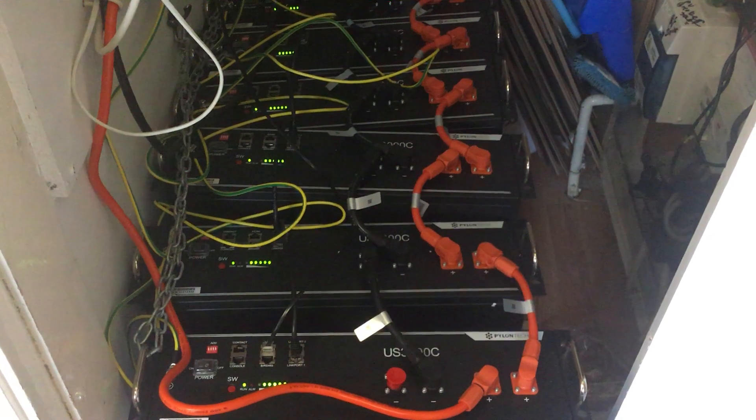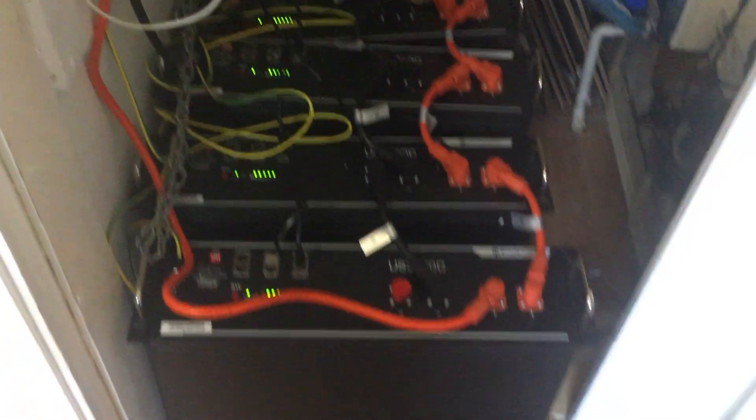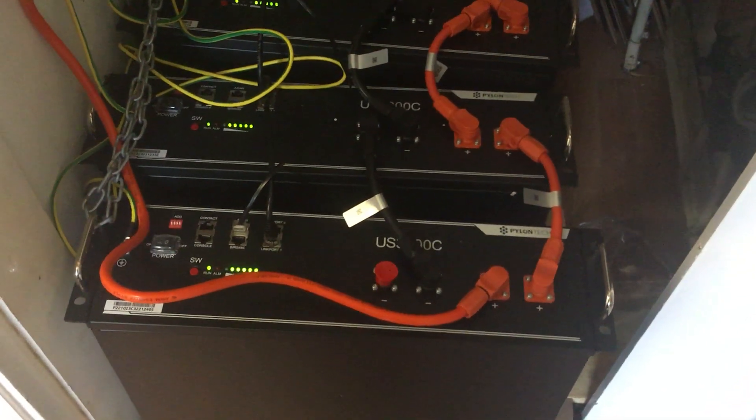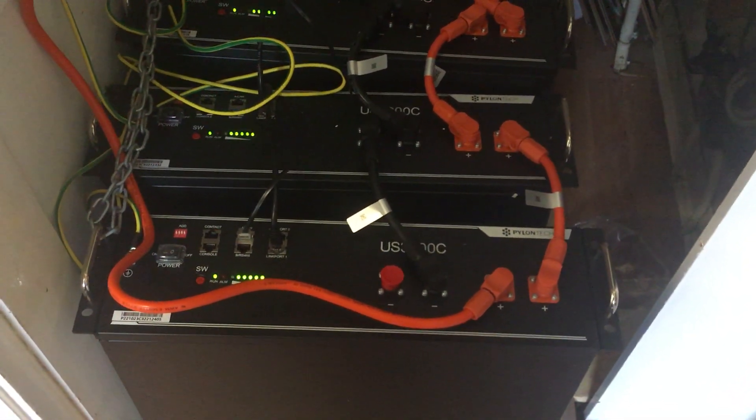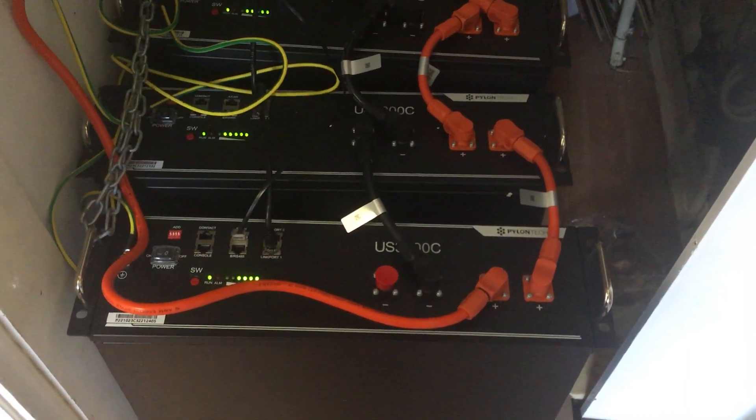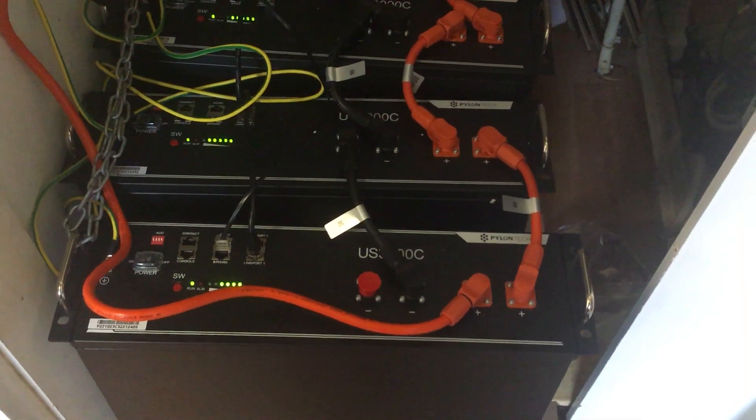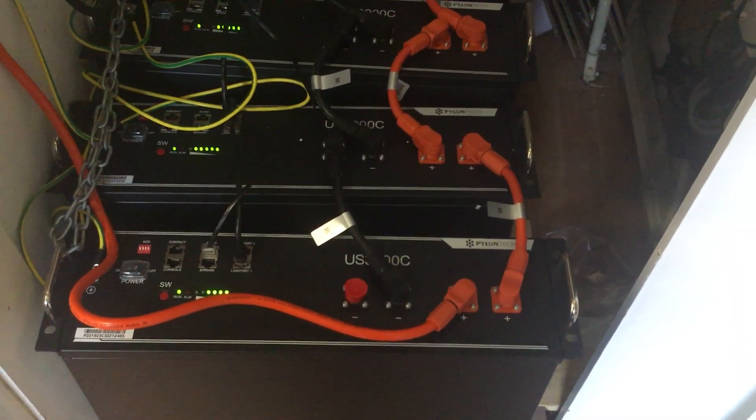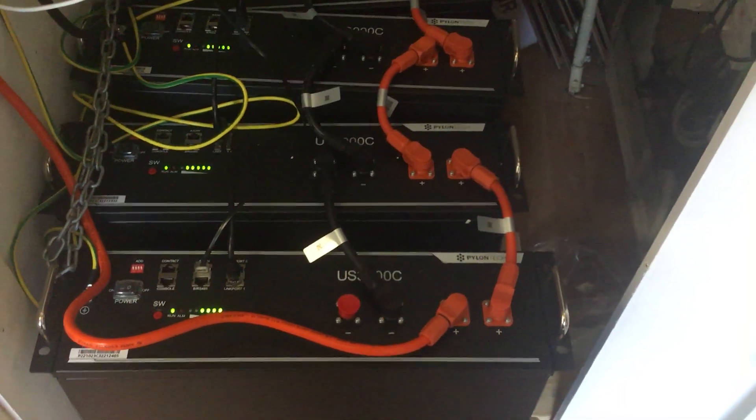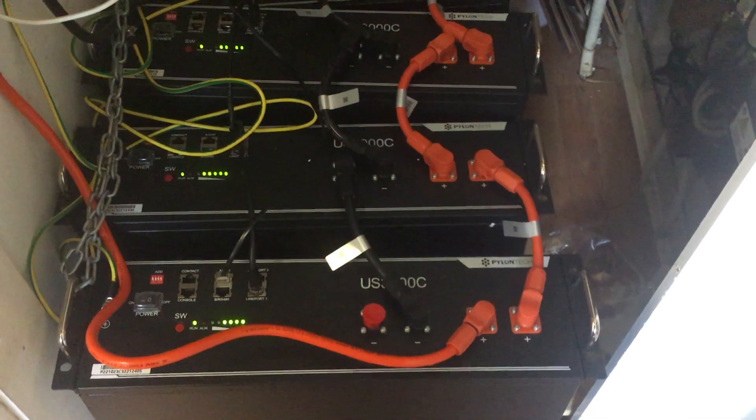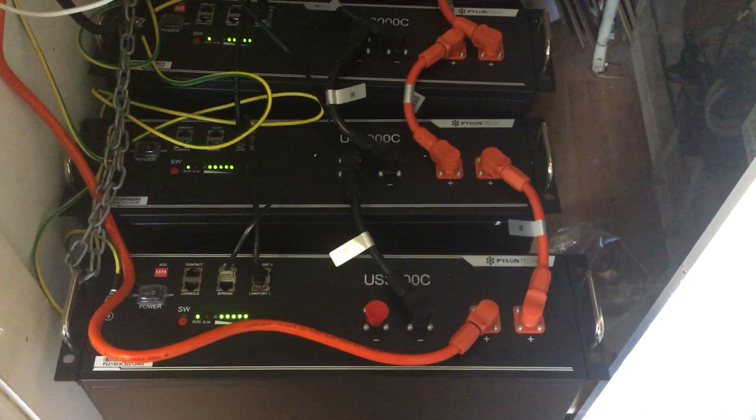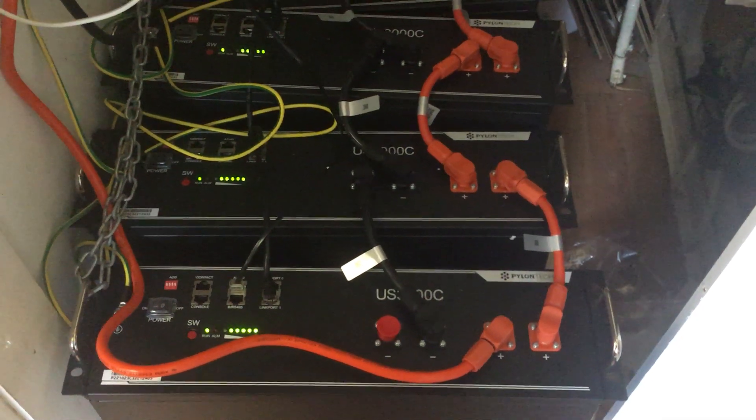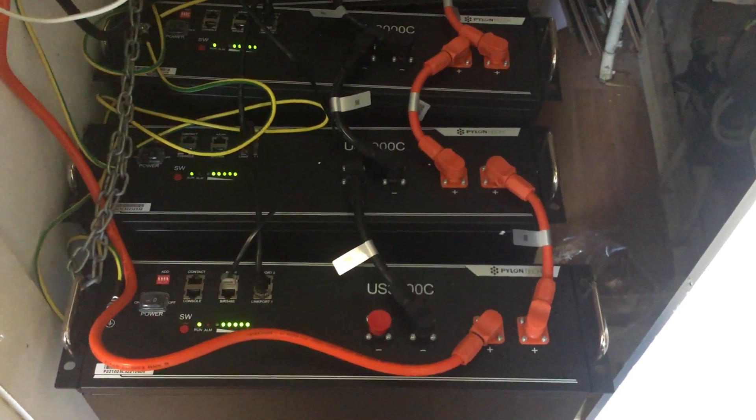Now this is caused by a number of faults and it could be wiring. It could be your plus and minuses not connected together properly, so make sure they're firmly plugged in. You can hear a click when you put them in the leads and the power leads. And obviously to remove them, there's a little button on the side where you press the button with your fingernail then it just pulls off. They are designed to be locked on because of safety, so you need to not stress them, not just pull them. You need to press the button on the side and make sure they come out, and when they go back in they actually click.